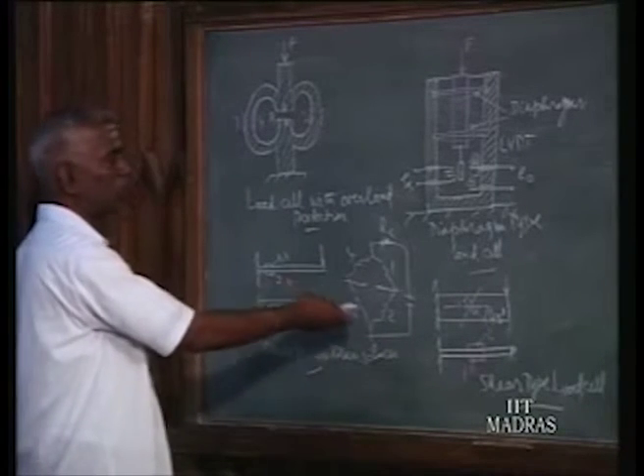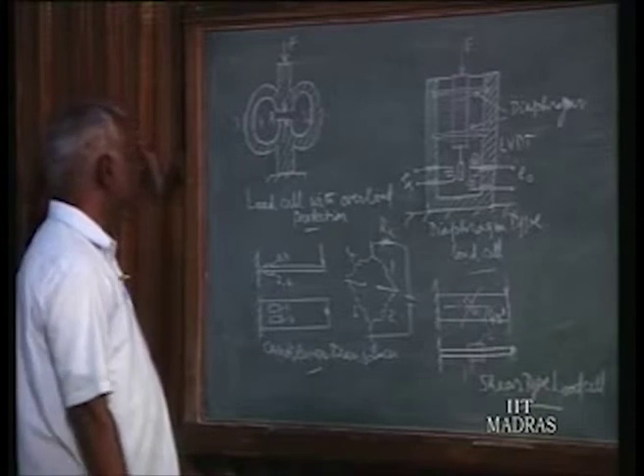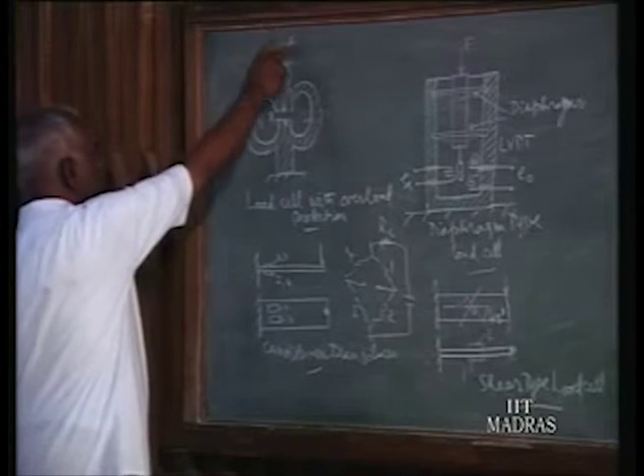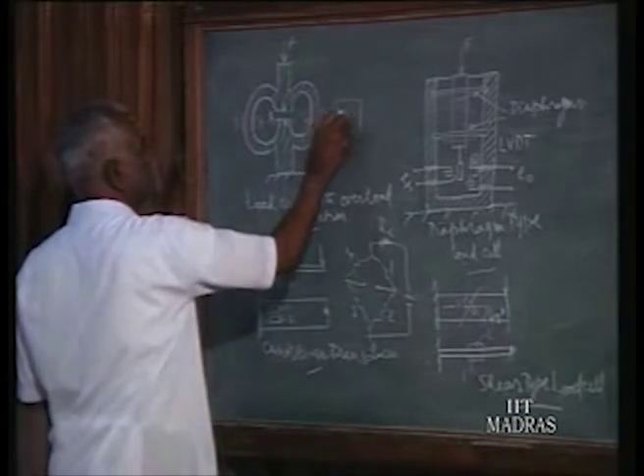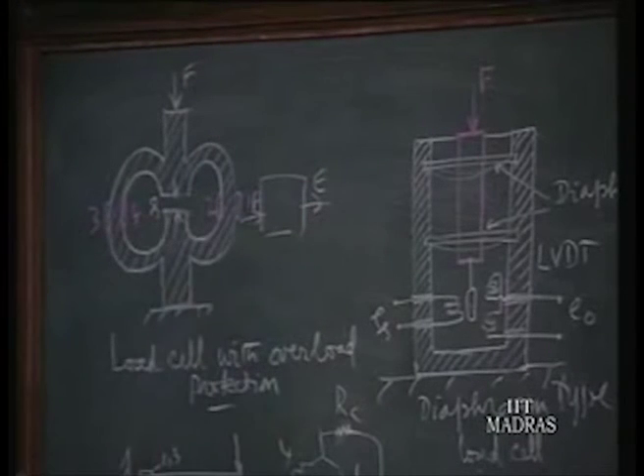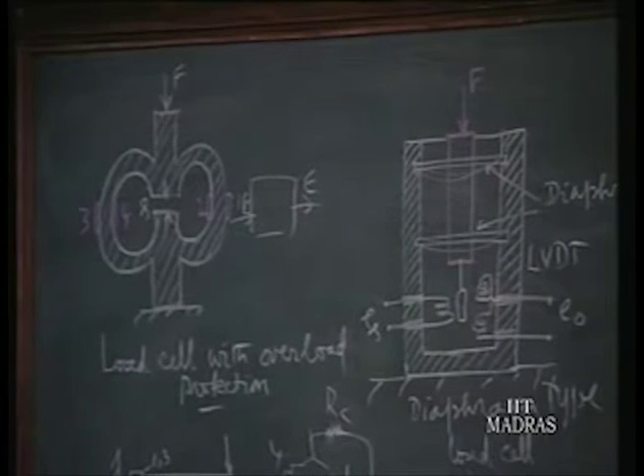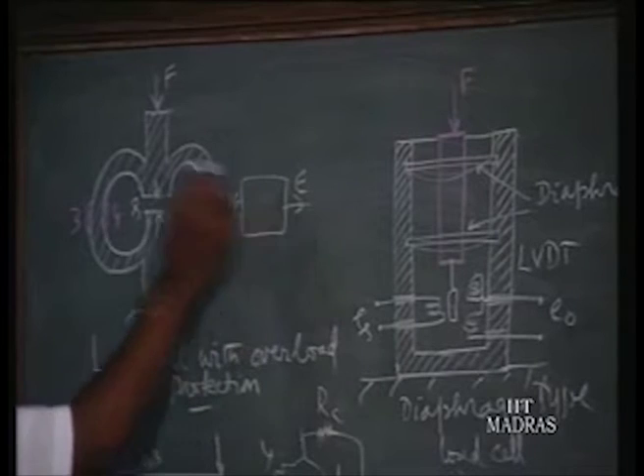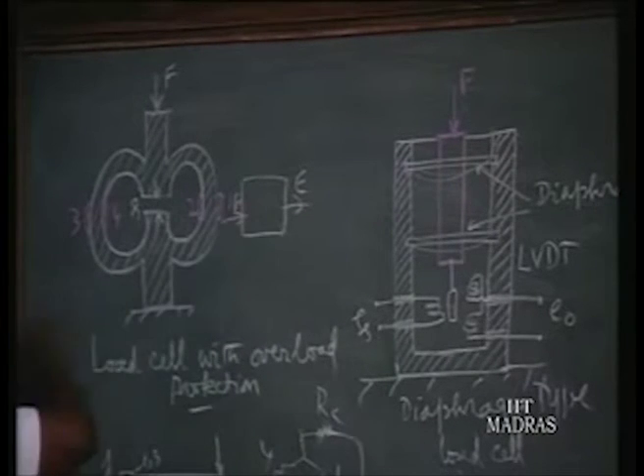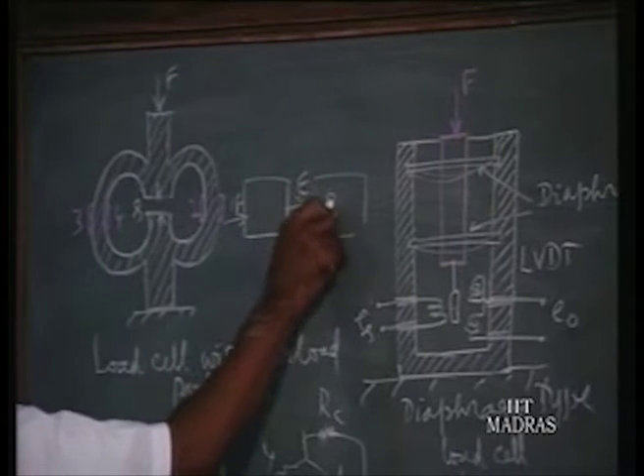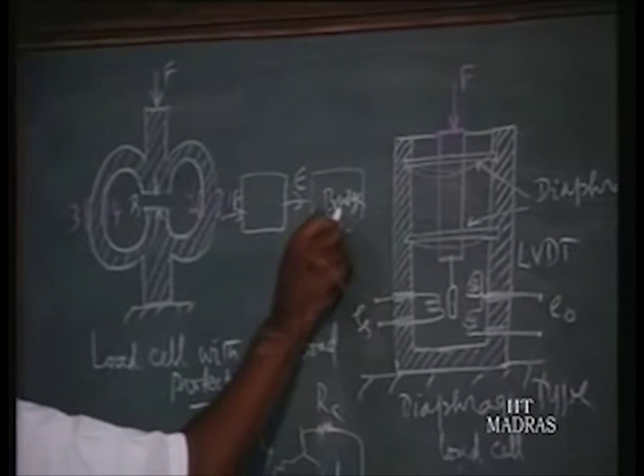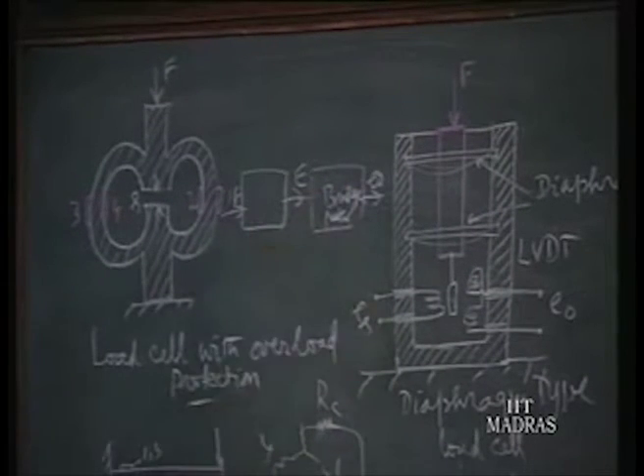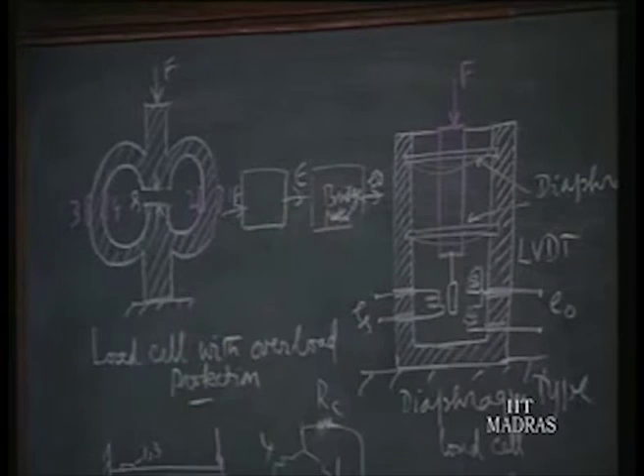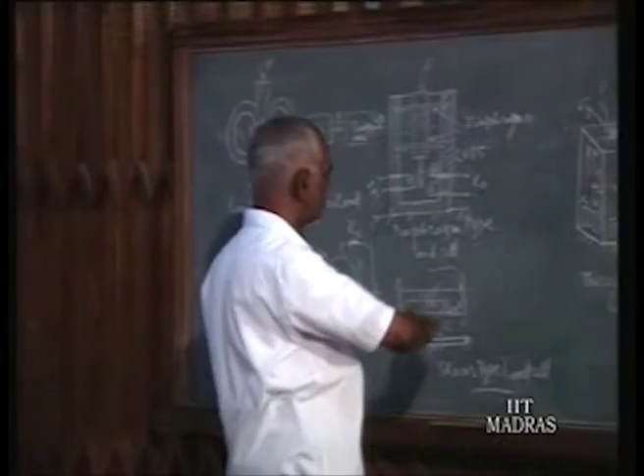That is the case in almost all the types where we use elastic members with strain gauges. We use one elastic member to transduce the force into strain. That is the block diagram. The force is converted into strain, either in the cantilever or in the proving ring or in the load cell. This is the primary transducer, the load member. So this is to be properly designed so that sufficient stress and strain is there. And then later on we give this to a bridge network, and from there we get an output voltage. This is the instrumentation. This output voltage is further amplified or read according to the situation. So more or less you will find two transducers, epsilon to E0, either the LVDT or strain gauge, anything we can use.